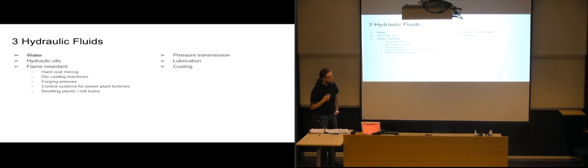But also, the hydraulic fluid acts to cool the equipment that we're using. So it's cooling it as we are using it, because fairly cool fluid is being transported from the reservoir through the system, maybe into a motor that's running pretty hard, so it's starting to get warm. But there is constantly a fairly cool hydraulic liquid that's being pumped into it and then sent out of it. As it's inside the rotating motor, it will be getting a lot of the heat transfer from the motor into the hydraulic oil, but then it will continue on in the system.